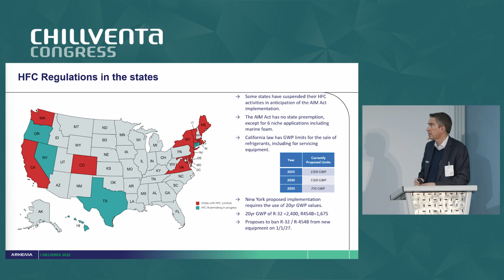Now, what California has done is pass a GWP limit for the sale of refrigerants, including servicing equipment - so not just new equipment, but aftermarket servicing. And I say in this table 'currently proposed limits', but it's actually current limits - this is the rule now. It doesn't really affect the HVAC industry much in 2025, but in 2030 it will have a big impact. It means 410A is completely gone - not allowed unless it's reclaimed. And then in 2033, it steps down even further.